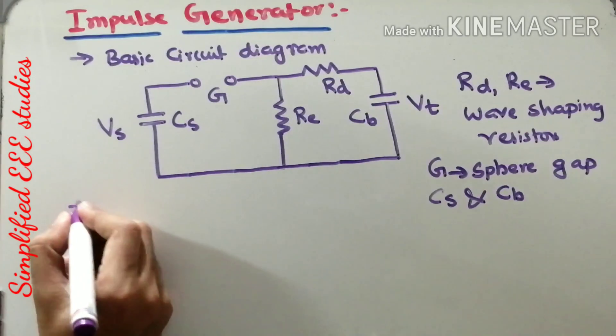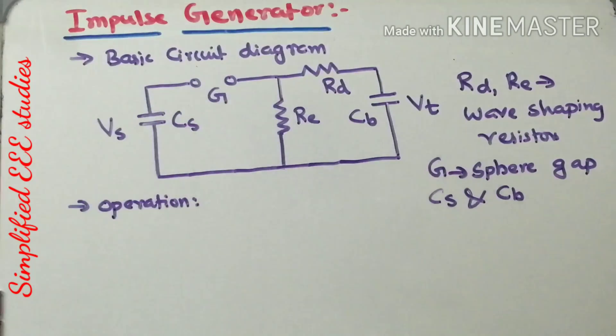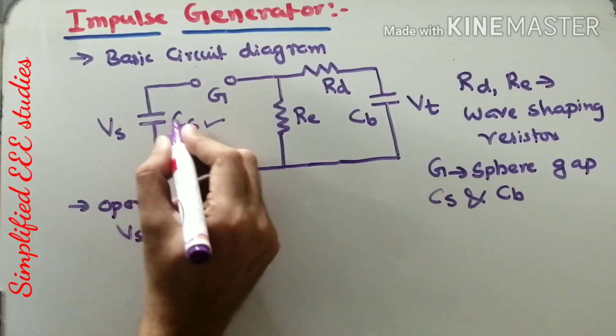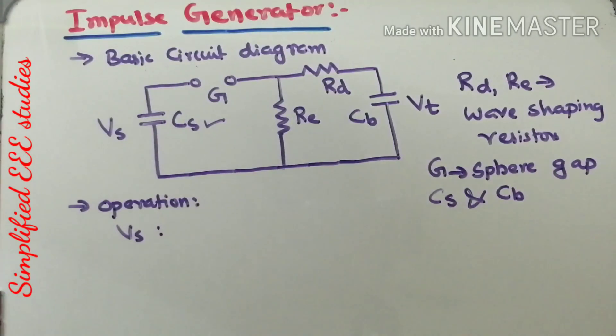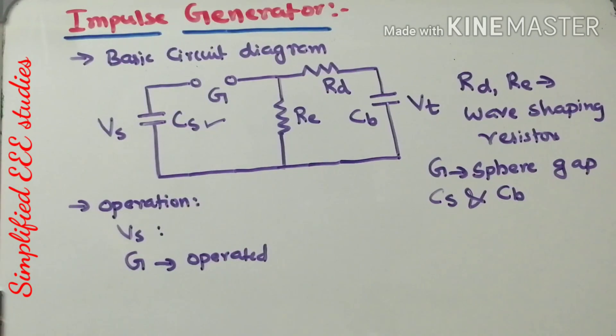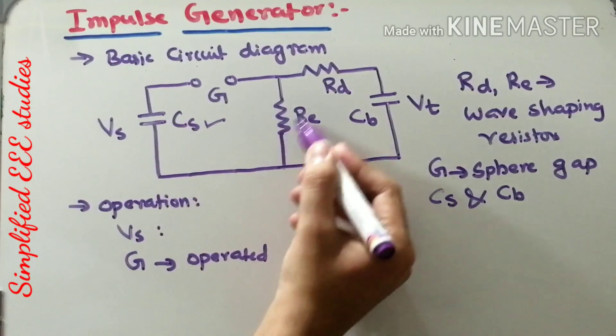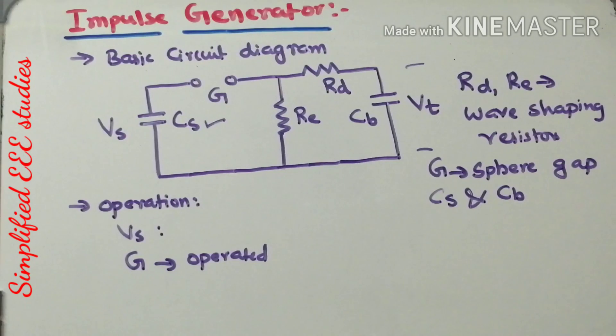Let us see how it operates. The impulse generator mainly works based on the charging and discharging action of a capacitor — specifically the charging and discharging action of capacitor CS. First, you need to apply input voltage Vs. Whenever Vs is actually reaching its peak value, the sphere gap becomes conductive — that means the sphere gap is getting operated. Once the sphere gap operates, the charge stored in the capacitor discharges through the output circuit. You will be getting the impulse voltage across capacitor CB. That means it is all about charging and discharging action.